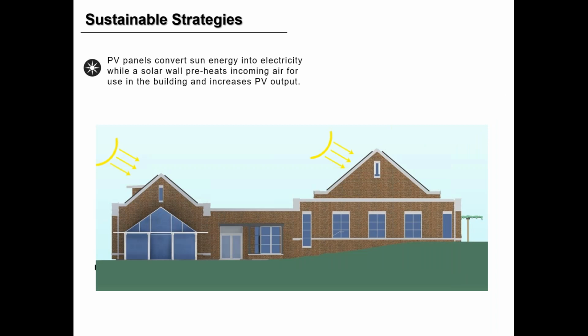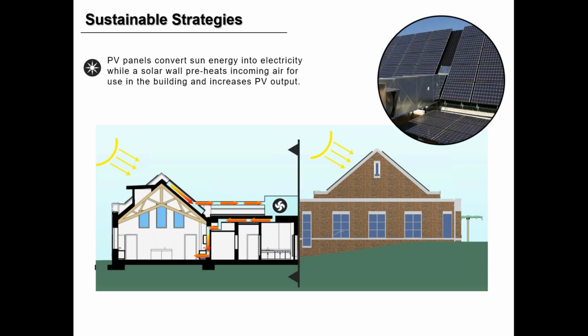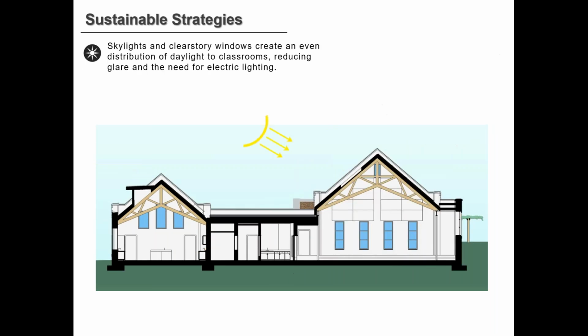The PV panels, again, are part of the generation strategy on the roof. You'll see in this picture the very tight coordination between mechanical ductwork and PV panels, which I'm sure was quite interesting. But again, the PV panels are preheating some of that air. We're dragging the air underneath the PV panels, taking the heat off the back side of the panel, and preheating the air before delivering it when we're in mechanical ventilation mode.